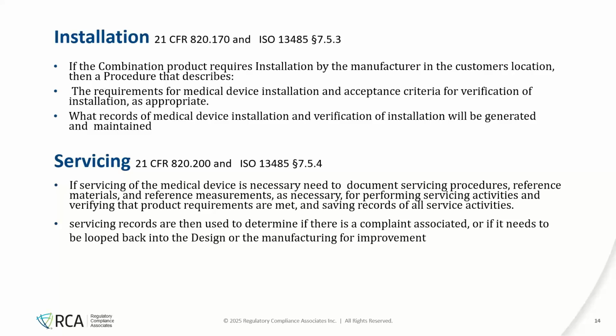If servicing is something that applies to your combination product, then you need to outline how that happens, what materials are needed, what tools are needed, what measurements they need to make, or confirmatory activities need to be done, what records you're going to keep regarding servicing that occurs. And if this was associated with a complaint, it would need to be looped back into the complaints process and/or the risk process and/or the design file.